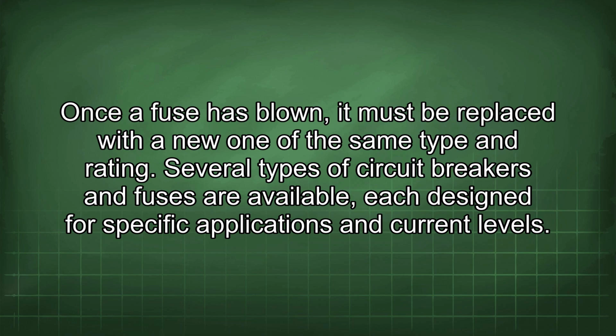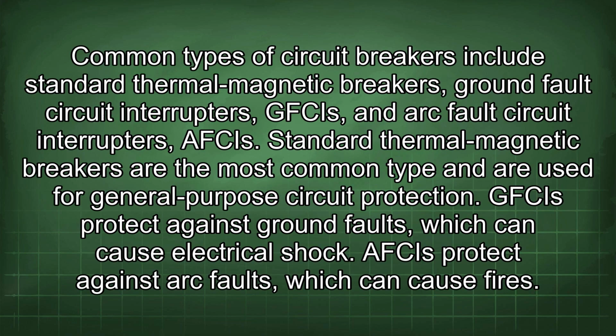Several types of circuit breakers and fuses are available, each designed for specific applications and current levels. Common types of circuit breakers include standard thermal magnetic breakers, ground fault circuit interrupters, GFCIs, and arc fault circuit interrupters, AFCIs. Standard thermal magnetic breakers are the most common type and are used for general-purpose circuit protection. GFCIs protect against ground faults, which can cause electrical shock. AFCIs protect against arc faults, which can cause fires.